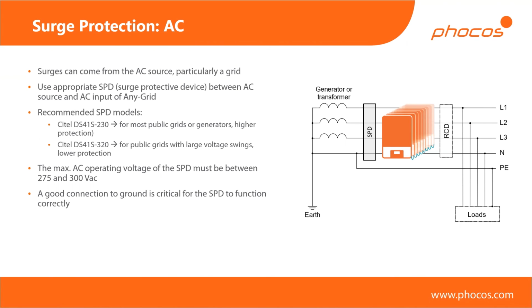Then for surge protection, as with almost any inverter from any respectable brand, there is some surge protection integrated into the unit on the PV side, the AC input side, the AC output and the battery as well. But all of these have their limits, of course, and an external surge protector will always do a lot more, with higher current ratings, to be able to swallow a lot more energy and direct it towards ground. So I would always recommend surge protection, at least on the PV side, as you'll see in the next slide, but also on the AC side.